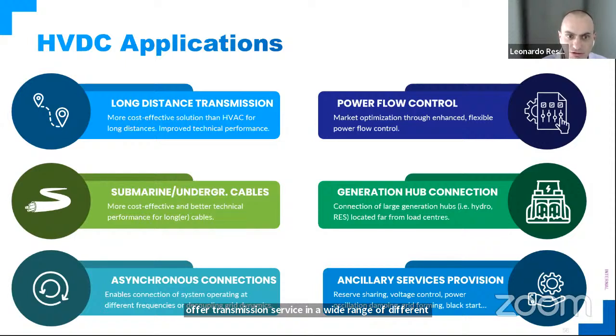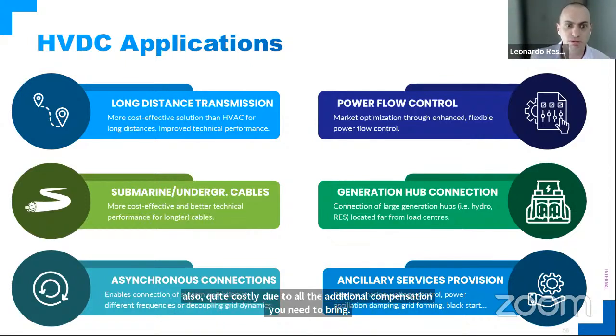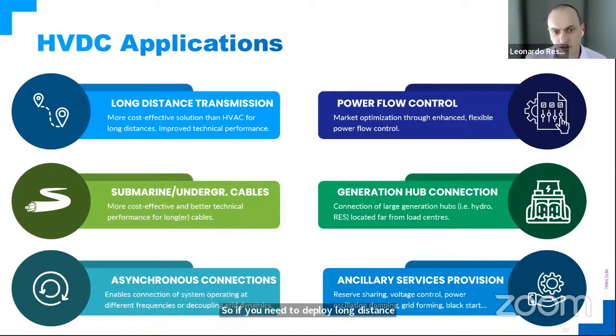A very classic application of HVDC, probably one of its first applications, is long distance transmission - more cost effective and technically performant than HVAC over long distances. The second is longer submarine or underground cable applications. Whenever you deploy cables longer than 40-50 kilometers, deploying them in AC becomes technically challenging for managing reactive power production, and quite costly due to the additional compensation needed. So for long distance submarine or underground cables, HVDC is usually the technology of choice.